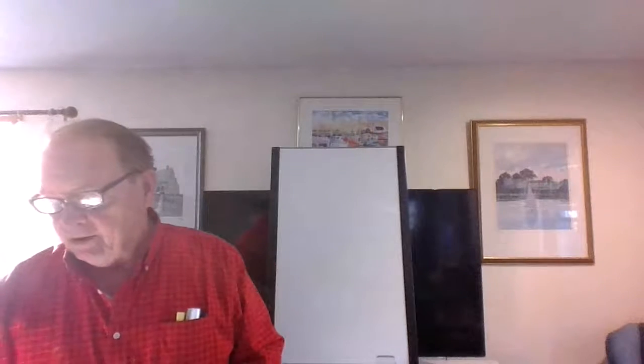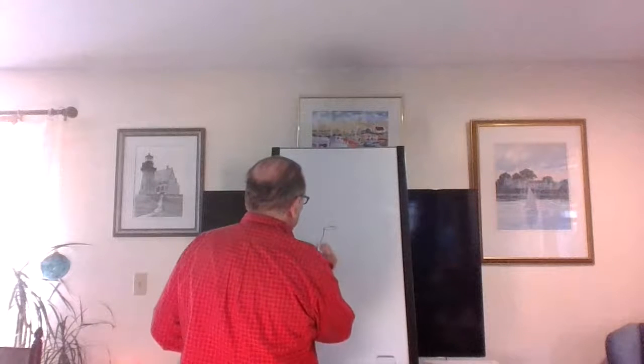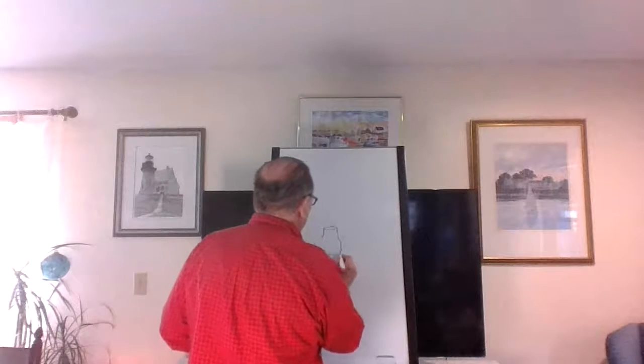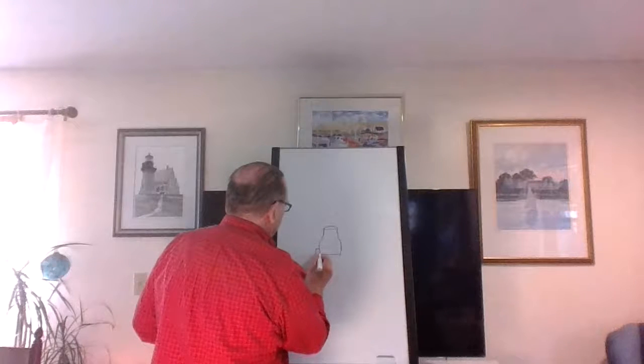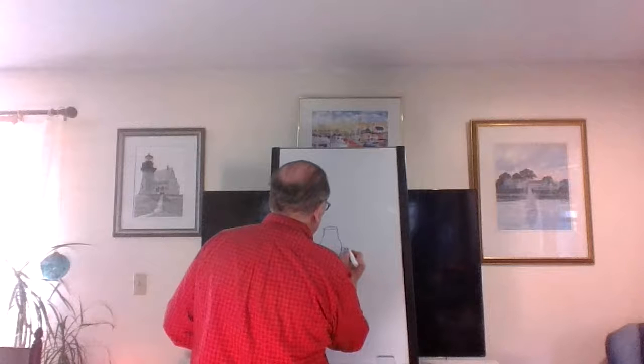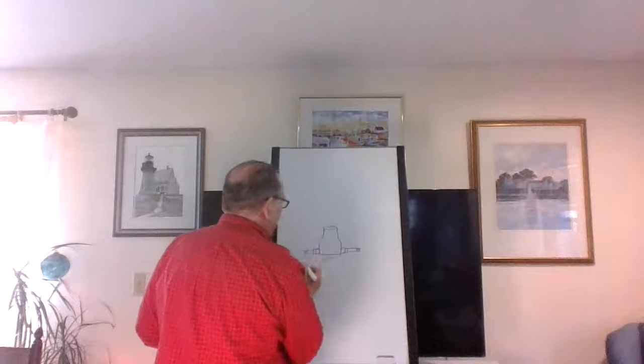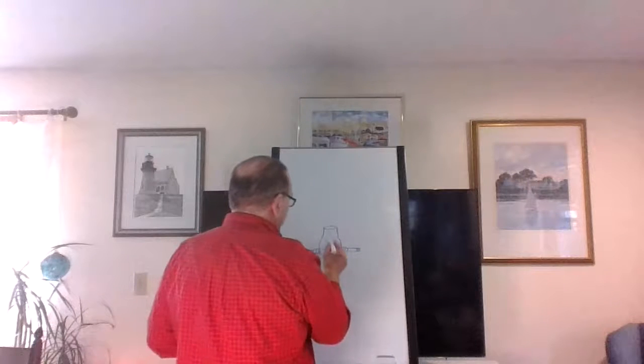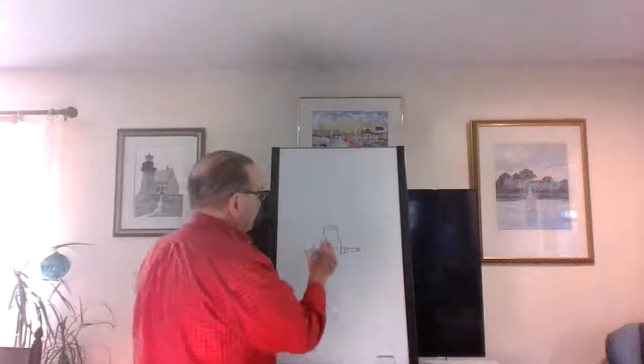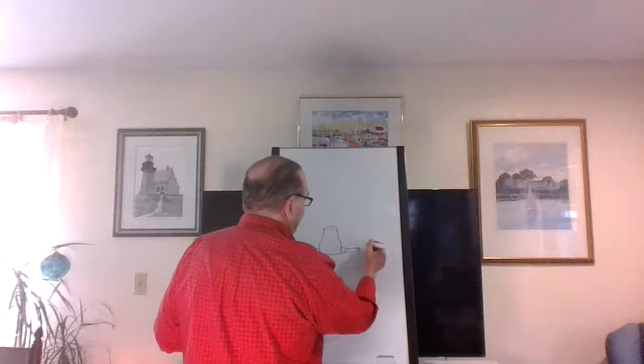Now one thing I'm going to mention, but we are not responsible for technically, it's not plumbing, is a meter. I think we even sketched it out. This could be half inch or three quarter, whatever it is. Now the meter is right here and you read it up on the top. The plumbing system starts on the house side of the meter. This is the house side, this is the outside going to the street. So on the house side, that's where we pick it up. We'd have a shutoff right here.